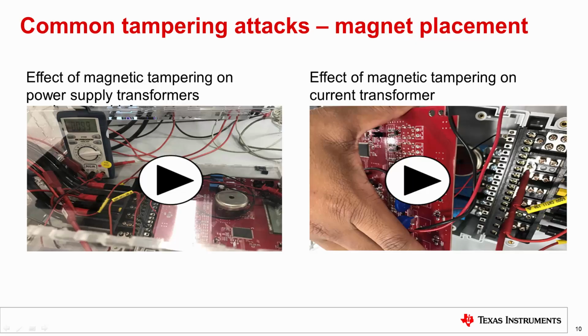One method to deal with the effect of magnets on CTs is to try to shield the magnet. However, CTs can only be shielded to a certain point. Due to this, shunt sensors are typically used for systems that should be magnetically immune. In addition, it is also common to detect strong magnetic fields and take special actions when a strong magnetic field is detected.